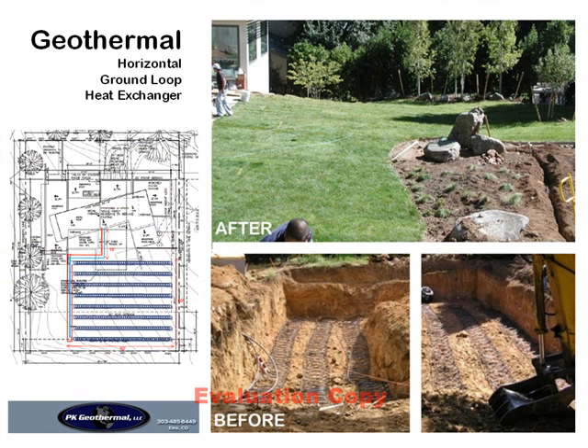The geothermal heat pump system is connected to a horizontal ground loop heat exchanger, buried 7 feet below the backyard. The horizontal ground loop heat exchanger cost approximately 20% less than the cost of drilling and was installed by PK Geothermal of Erie, Colorado.